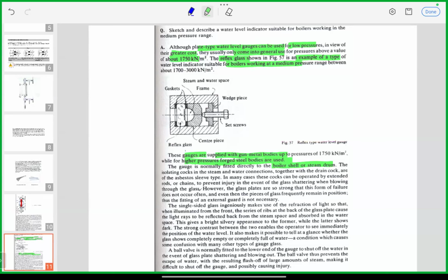And for high pressure, steel bodies are also used. The gauge is normally fitted directly to the boiler shell or the steam drum. The isolating cocks in the steam and water connections, together with the drain cocks, are of the asbestos sleeve type, with sealing given on both sides of the cocks. In many cases these cocks can be operated by extended rods or chain, with remote operation using pulling handles and cables.